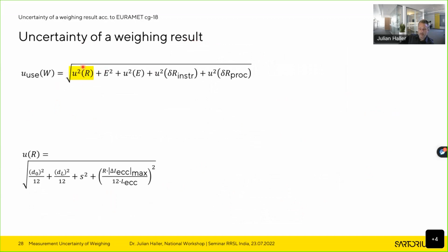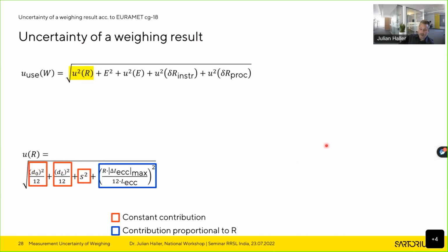So we know already this one, the uncertainty of any reading, mentioned that: uncertainty of rounding at zero, rounding at load, standard deviation of repeatability, and eccentricity. So that is what we've seen before. And the good thing about all uncertainty contributions that we will consider in the following is that they can be assumed to be either constant, so it's a constant value over the complete weighing range, or roughly proportional to the reading or to the load.